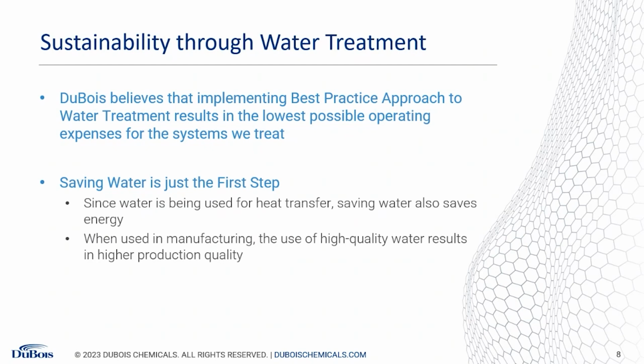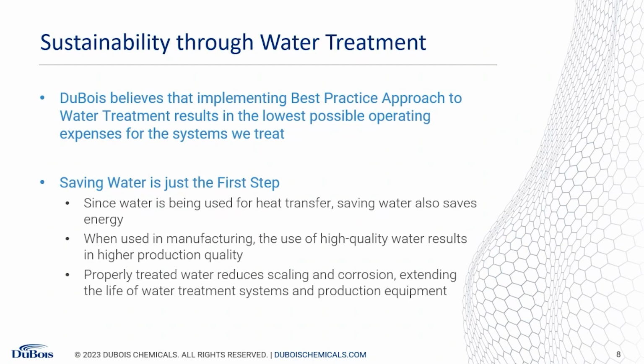When used in manufacturing, if you want high quality results, you need high quality water. Think of a molding process: you're putting something, plastic or metal, liquefied so it can go into a mold, then you cool it quickly so it sets. If the water has scale or a tendency to scale—too high a calcium level, too high a carbonate—that scale will form on the outside of the mold and affect the heat exchange, so you won't get your cooling done in the designed time, which could cause defects.